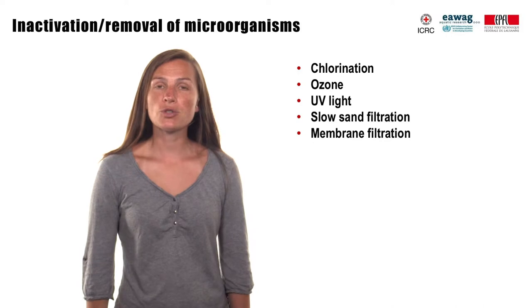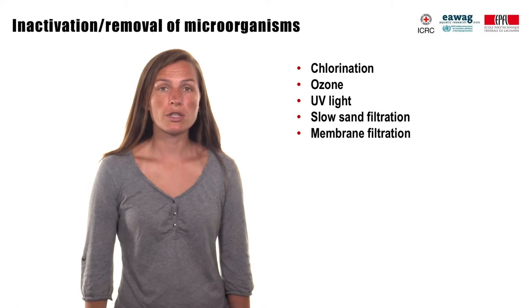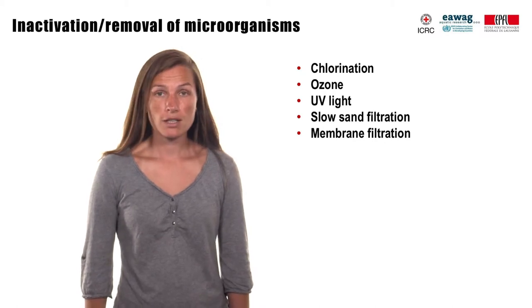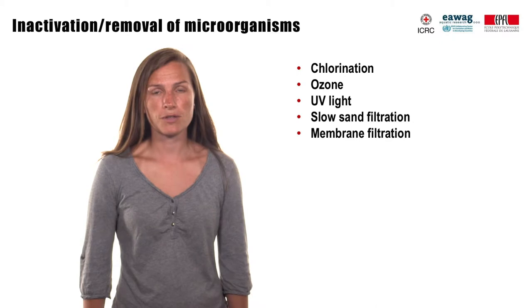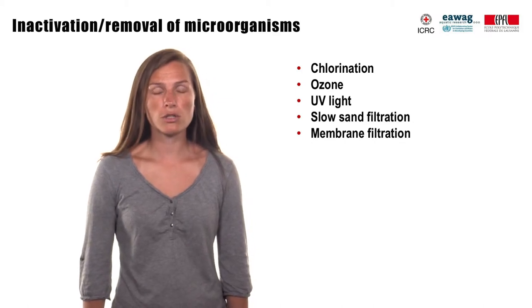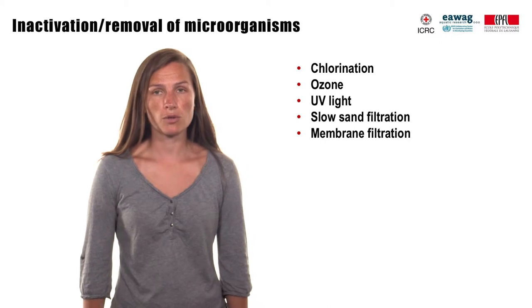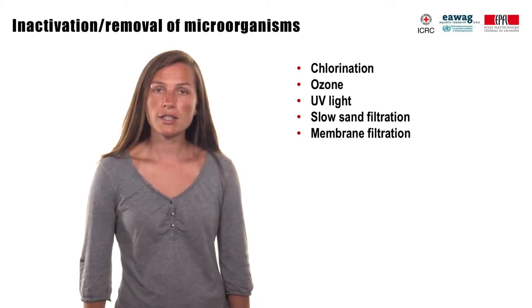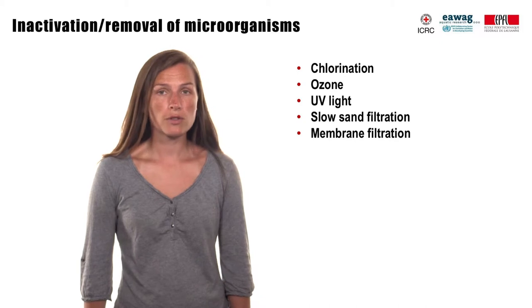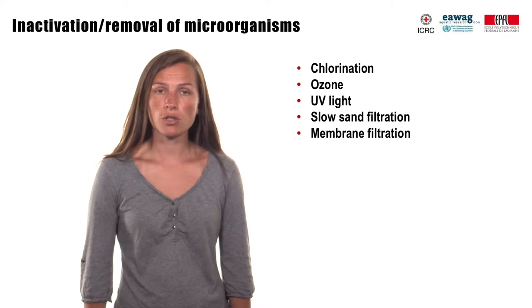Disinfection of drinking water ensures that bacteria, viruses and protozoa have been inactivated or removed from water so they no longer pose a health risk. Disinfection is always done after clarification and not before, as particles reduce the efficiency of many disinfectants. Disinfection by chlorination is the most commonly used method. Ozone and UV light inactivate microorganisms, while slow sand filtration or membranes are based on filtration, purely or combined with biological processes.